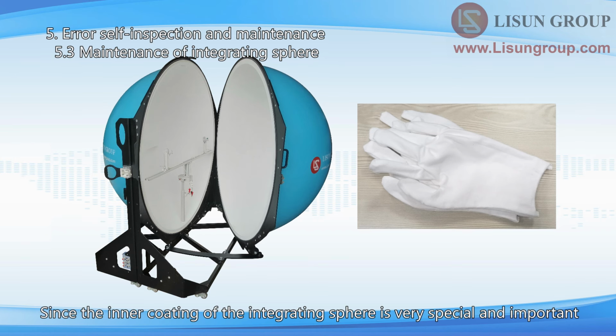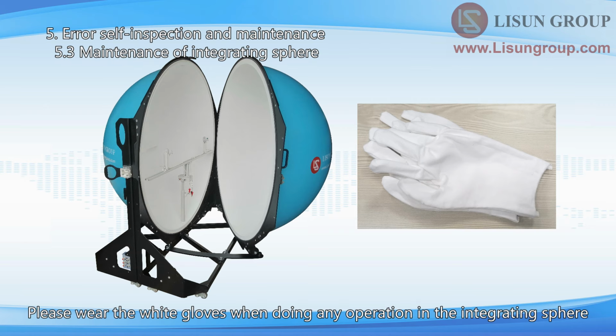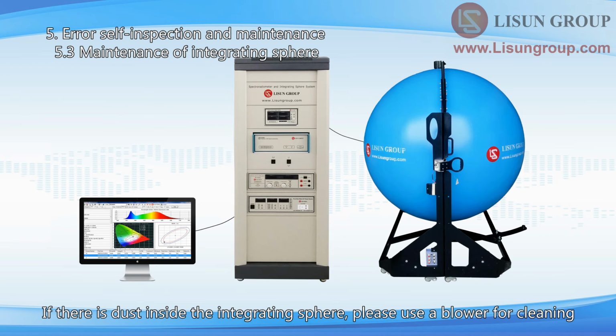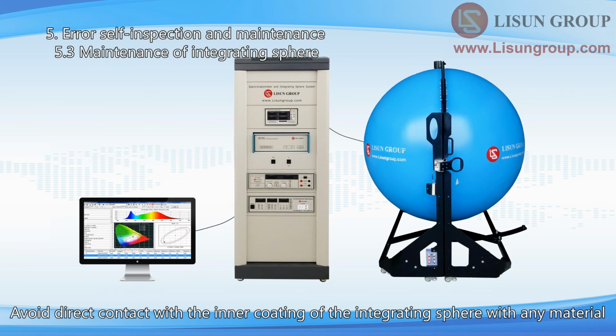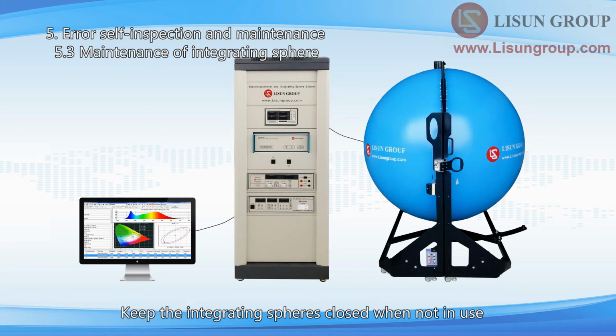Since the inner coating of the integrating sphere is very special and important, please wear white gloves when doing any operation in the integrating sphere. If there is dust inside the integrating sphere, please use a blower for cleaning. Avoid direct contact with the inner coating of the integrating sphere with any material. Keep the integrating spheres closed when not in use.